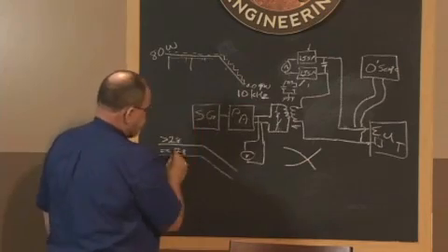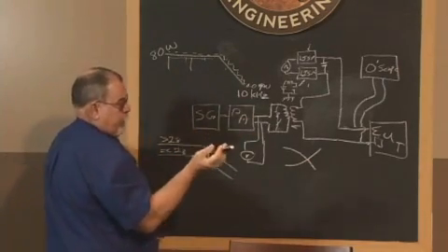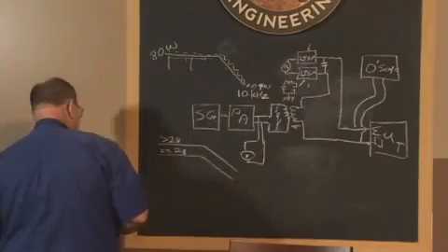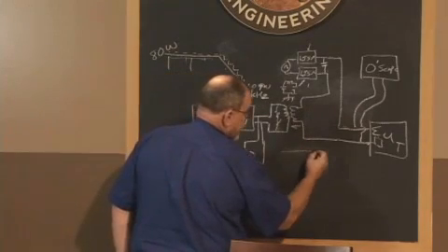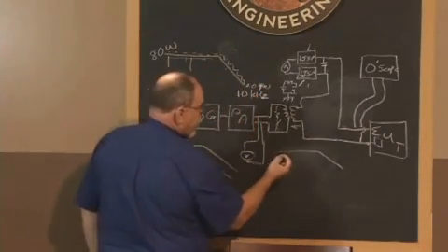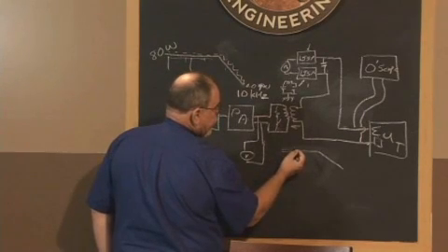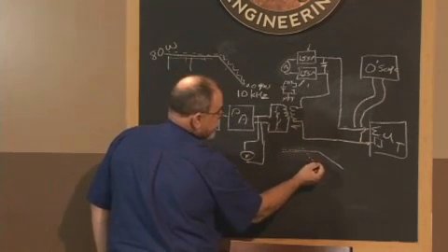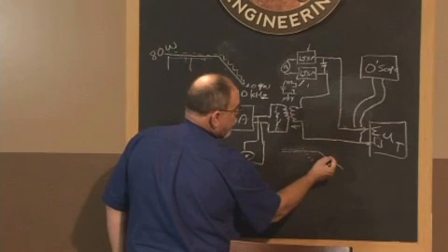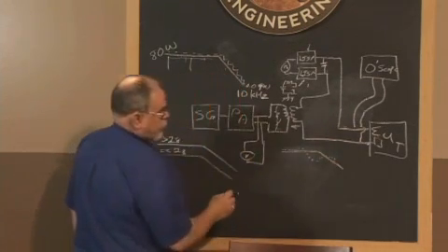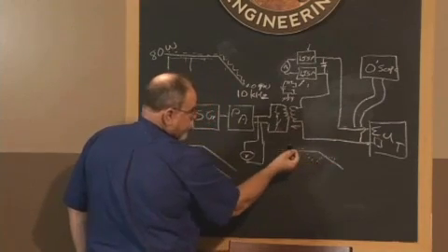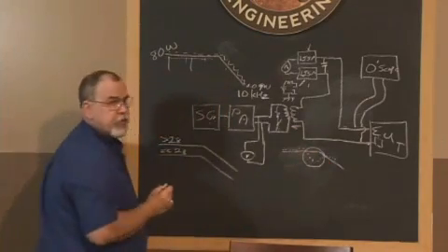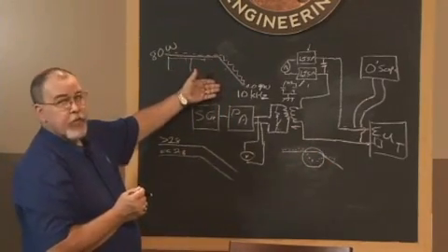As we go through the test frequencies, we're providing this, and when we start doing the actual testing, we start creating the applied voltage. In our data collection, we have a process of the chart showing the limit, and we're applying the voltage points above that limit, and suddenly we can't get there. And that indicates that we have hit this forward power point. So we're creating an applied voltage that follows a curve differently than this. In this region, where we're below the limit, we're assuming that we were applying these pre-calibrated numbers.